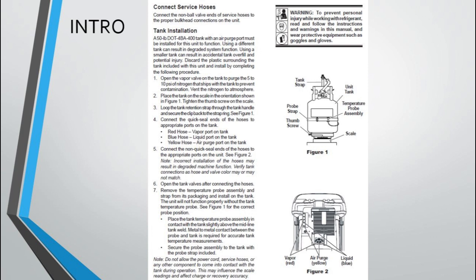6. Open the tank valves after connecting the hoses. 7. Remove the temperature probe assembly and strap from its packaging and install on the tank. The unit will not function properly without the tank temperature probe. See Figure 1 for the correct probe position. Place the tank temperature probe assembly in contact with the tank slightly above the midline tank weld. Metal-to-metal contact between the probe and tank is required for accurate tank temperature measurements. Secure the probe assembly to the tank with the probe strap included.